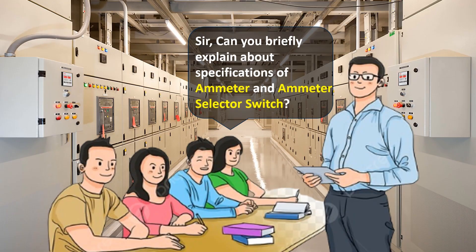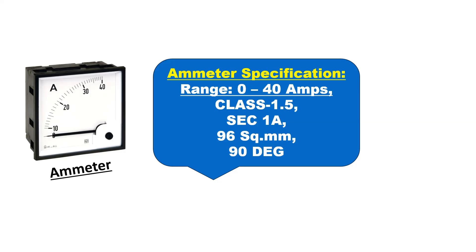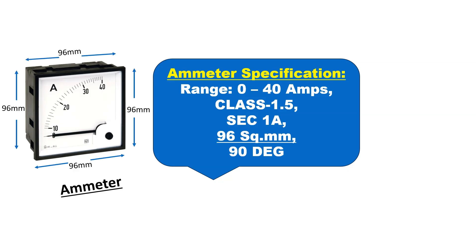The ammeter specification range is from 0 to 40A, which means it can measure electrical current from 0 to 40A. Class 1.5 refers to the accuracy of the ammeter, meaning it has an accuracy of plus or minus 1.5% of the reading. Secondary 1A indicates that when the ammeter receives a secondary current from the current transformer of 1A, the measured full-scale value will be 40A.